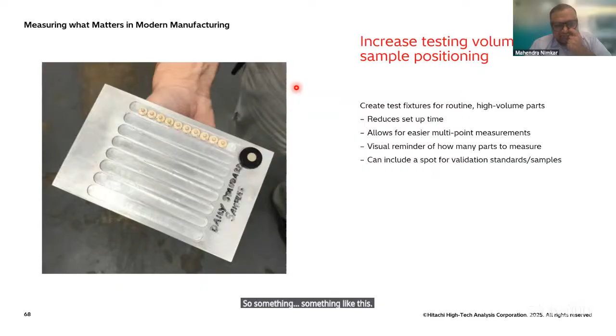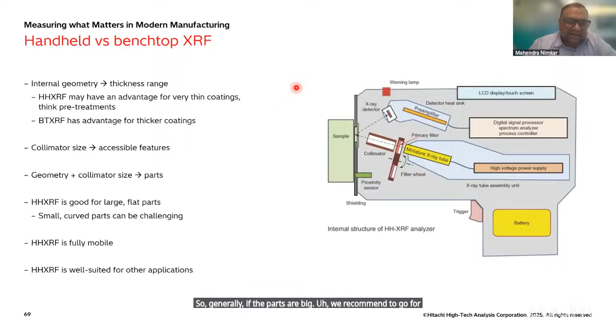As I mentioned, handheld XRF and benchtop XRF. Handheld XRF is also capable of doing single layer thin coatings. It generally gives better results when the coatings are thin and single layer, not multiple layer coatings. And if the parts are big, because in handheld XRF the collimator size or exposure area is very big, it's like 6 or something. So generally if the parts are big, we recommend going for handheld XRF.